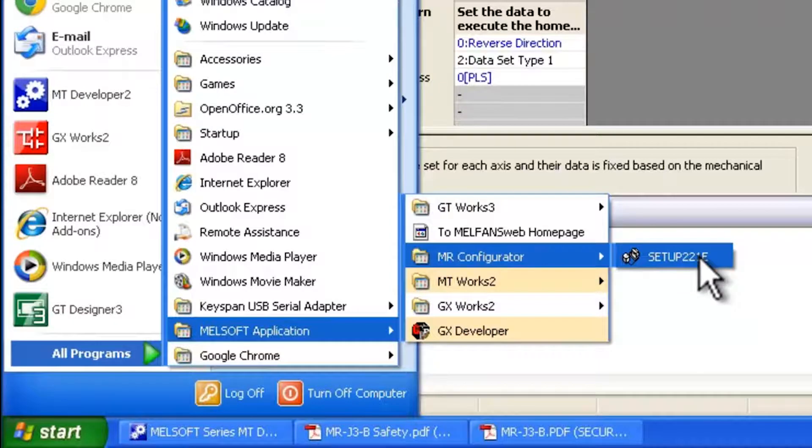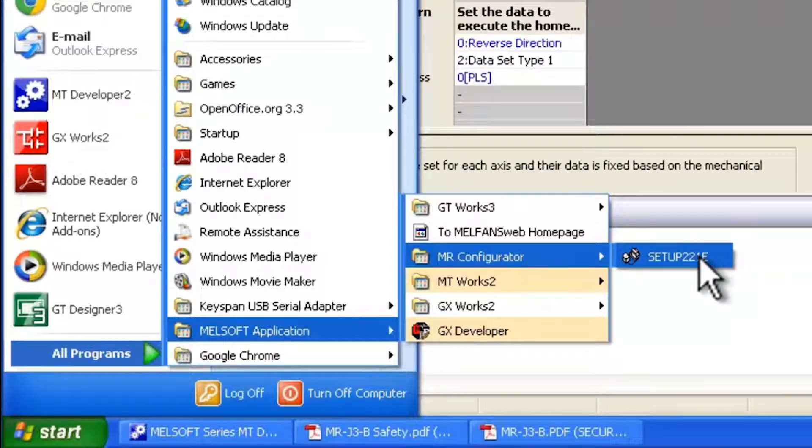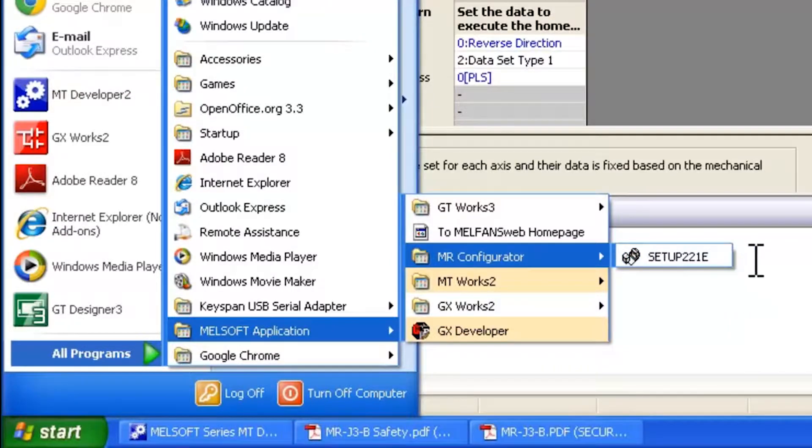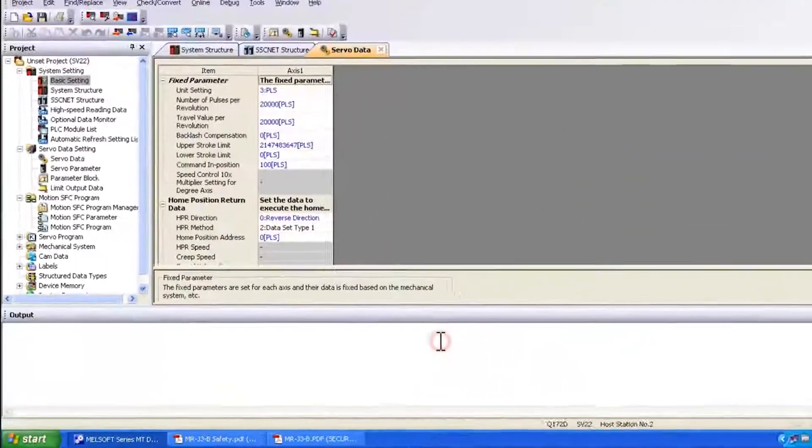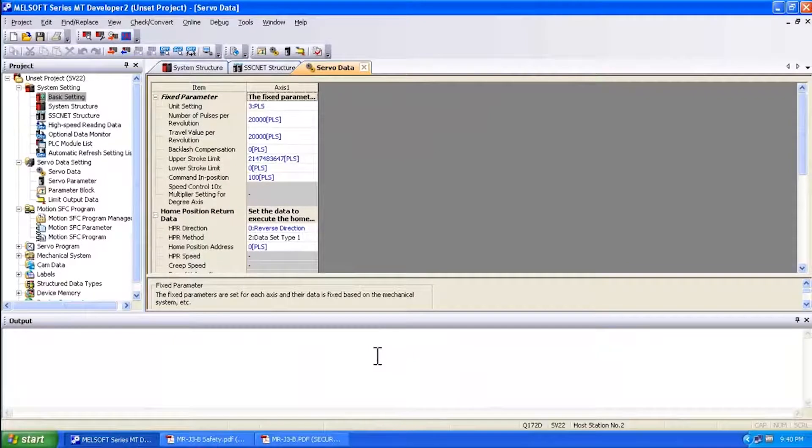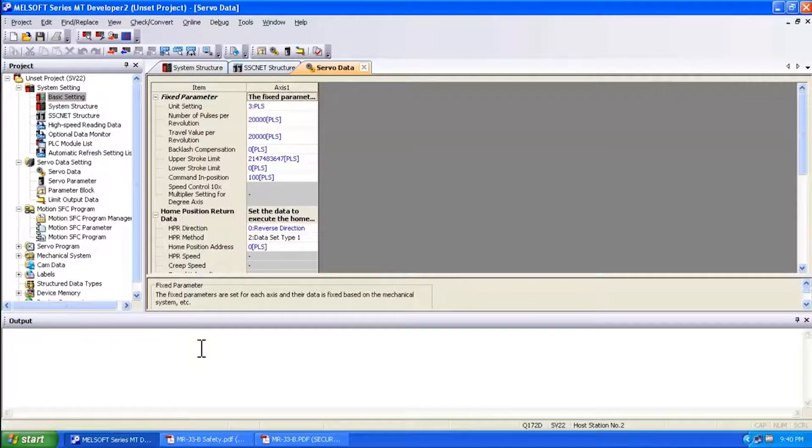Just a word of caution, please be careful whenever you use MR Configurator through the start menu to modify parameters. They will not be saved through your motion controller. So make sure that you access all servo parameters with your project through the MT Developer 2 software. It's very important. Otherwise, the parameter settings that get changed will not be remembered.